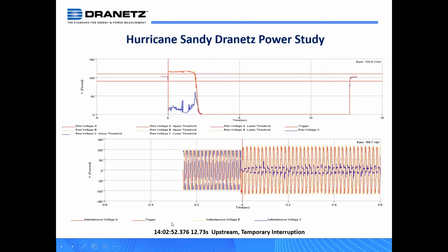So what you see here is the short happen on C, and A and B swell for about 2 to 3 seconds. Then the reclosure opens up and says, hey, I got a problem here. For safety reasons, I'm opening up. About 10 seconds later, it closes. All these reclosures out on the line do the same thing. So those that can close and stay closed are fine. Their circuits resume normal activity. Those that close and the short remains, those open back up and they clear that fault from the system that way. That's the way it would happen in the United States.